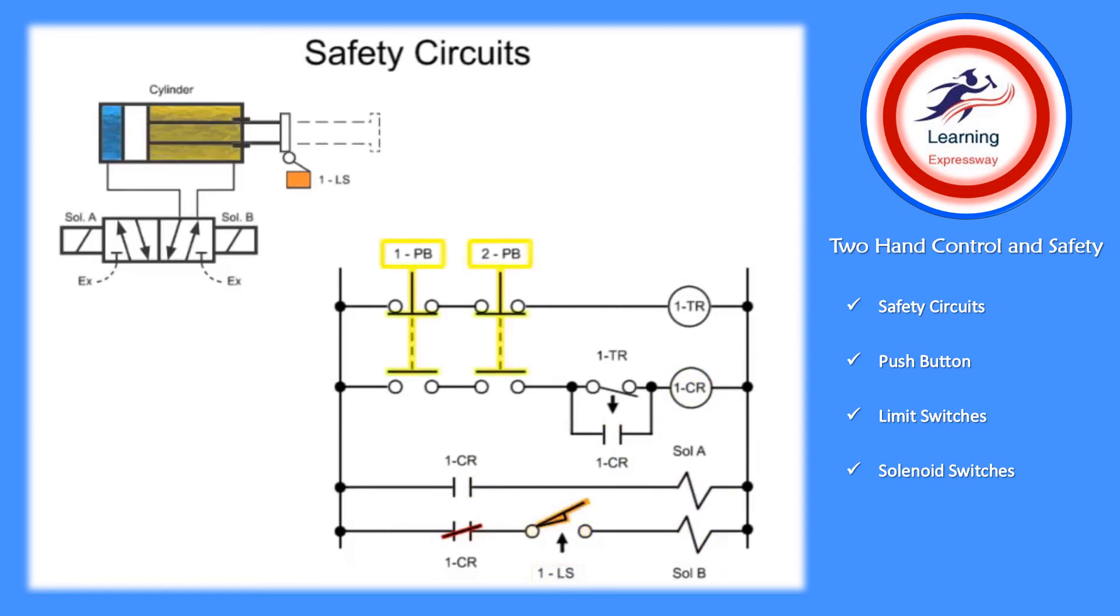When both push buttons are in the unactuated position, the timing relay is energized and the normally open-timed open-timer contact is shut. No power can flow to the control relay. If an operator depresses a single push button, power to the timing relay is removed and the off-delay timer starts to time.